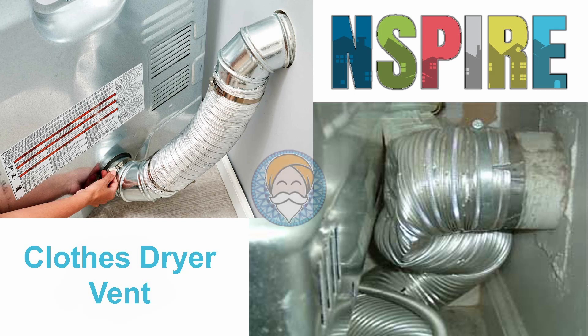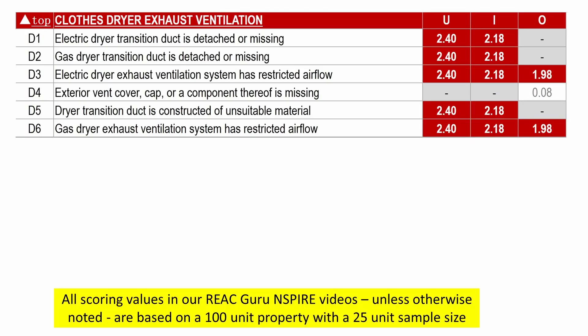Clothes dryer exhaust. This is another deficiency that's gone from one of the lowest scoring unit defects to one of the highest scoring. I was personally shocked when I first read this new standard. REAC is calling a disconnected or clogged dryer vent on an electric dryer life-threatening. In discussing this with one of my colleagues, I was told he had heard secondhand that they've justified this by statistics showing that fires are caused by dryer vent issues as often on electric dryers as on gas dryers. So where a laundry area deficiency for a dryer vent was typically worth about a tenth of a point on the old UPCS version of the REAC inspection, any dryer vent issue will now be worth 2.4 points under NSPIRE.